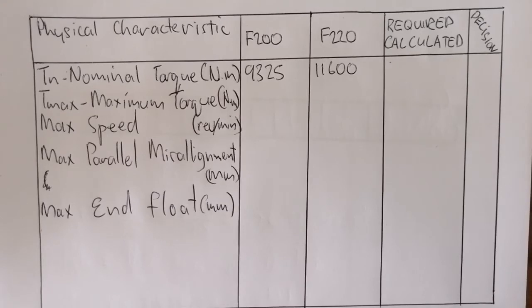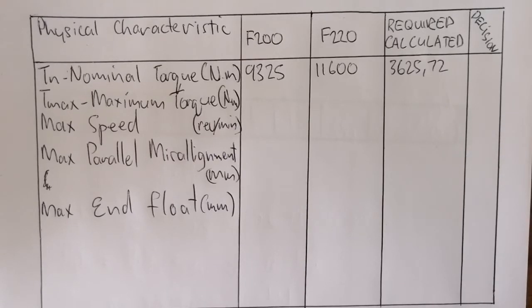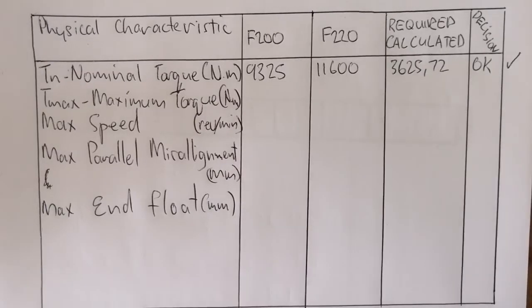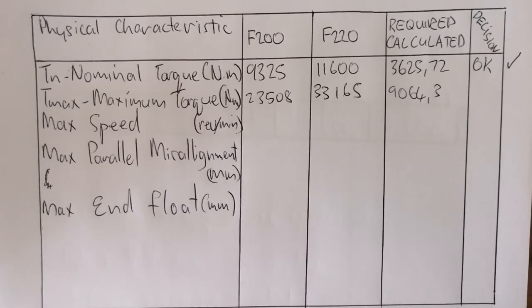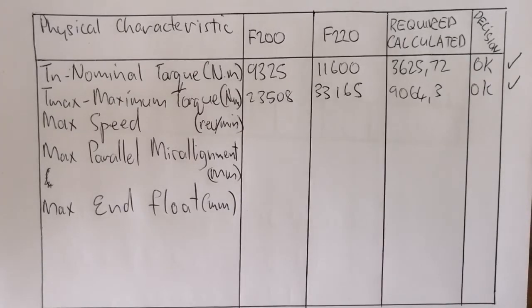There's the nominal torque for both F200 and F220. What have we calculated? 3625.72 newton meters. Is this okay or not? Since both can handle higher than the calculated or required, we write down okay. Next is the maximum torque - our calculated was 9064.3. The manufacturer gives that their couplings can handle 23,508 for the F200 and 33,165 for the F220. So we are happy with that result - okay.